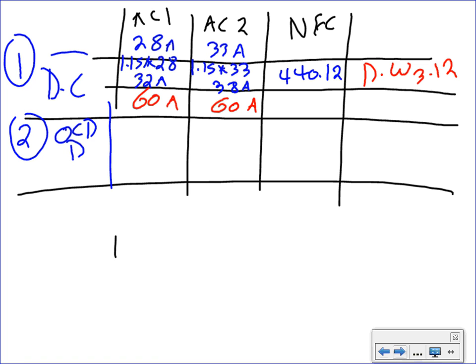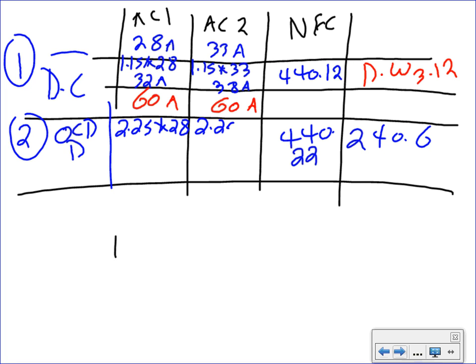If you guys go for this one, you need to go to 440.22 and also 240.6. If you go there, it will tell you first 175 percent, then it tells you 225 percent if it doesn't start. Always start with 2.25. So 2.25 multiplied by 28 and 2.25 multiplied by 33. Right to the 2.25, assuming it's not going to start, and we go down. You can't go 175.